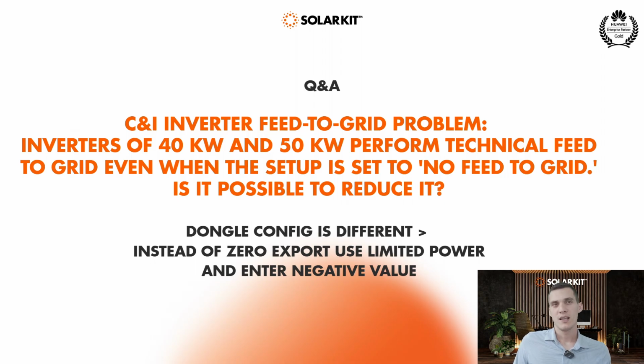And another question was the C&I inverter feed to the grid problem. Inverters of 40 and 50 kilowatt perform technical feed to grid even when the setup is set to no feed to grid. Is it possible to reduce it? It's absolutely possible. If the measurement is correct, then it's most probably because there are some kind of loads on the side which are turned off and consume a lot of power while they are working and shut down immediately. And the inverter cannot reduce its power that quickly. So it requires some kind of tolerance zone.